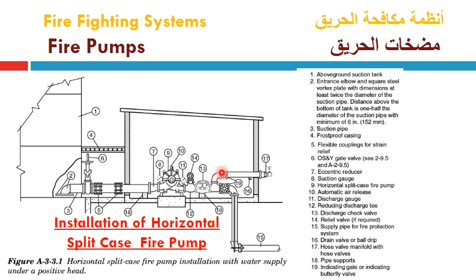And then we can use the bypass line to the test hose valve manifold with the hose valves shown as number 17, and then we can locate our indicating gate valve or indicating butterfly valve, which is rarely used in fire pumping systems. The commonly used one is the OS and Y gate valve, but here it is installed horizontally, instead of vertically as on the suction side. And then we can go to our fire stand pipe, which will provide the fire water to the supply pipe for the fire protection system, to the protected building, area or zone.